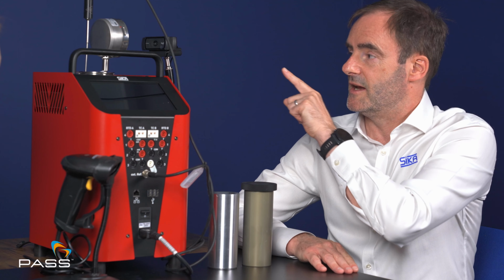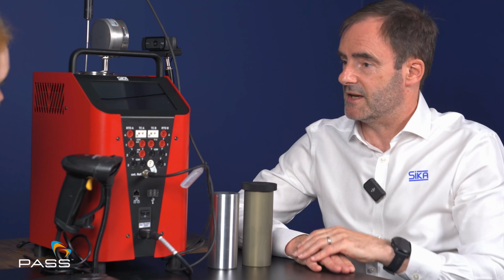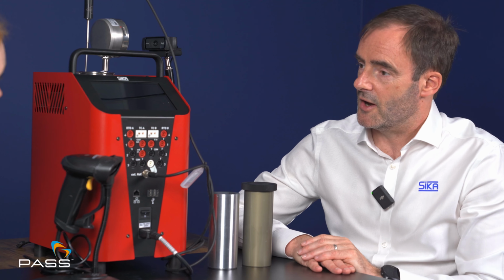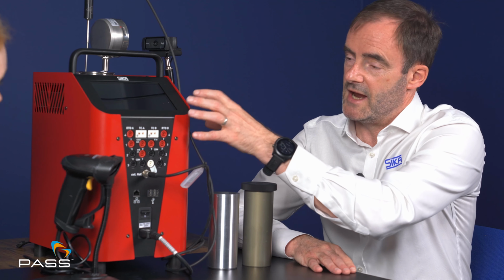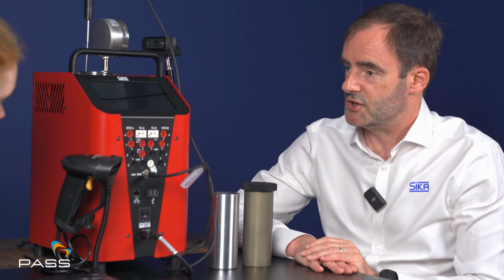We can also calibrate digital pressure temperature gauges. So on this particular scenario, we have a camera function where we can actually look at the digital readout from the device under test, and then we can correlate it with the actual temperature that the unit is actually generating.